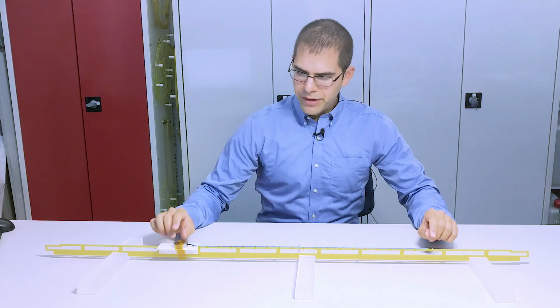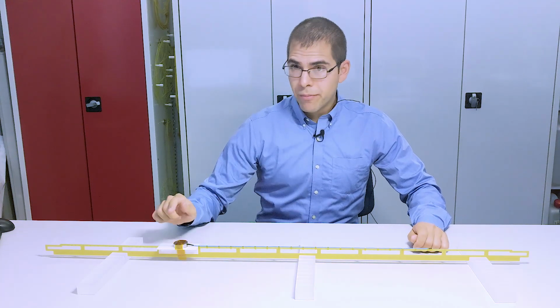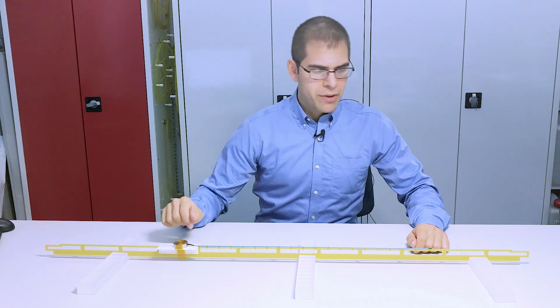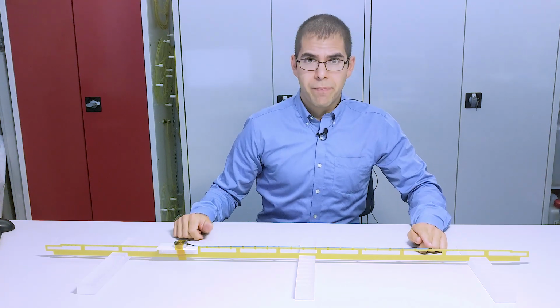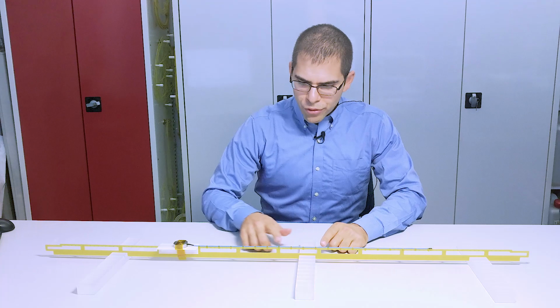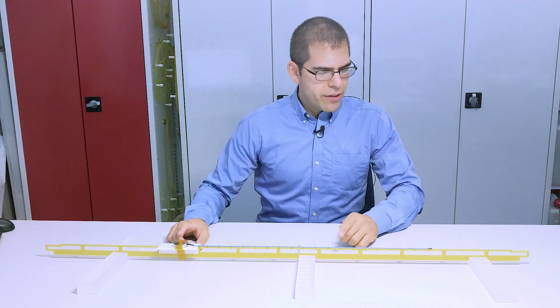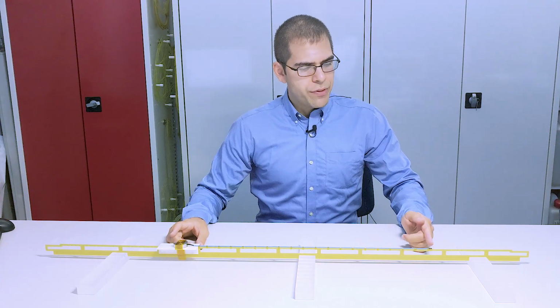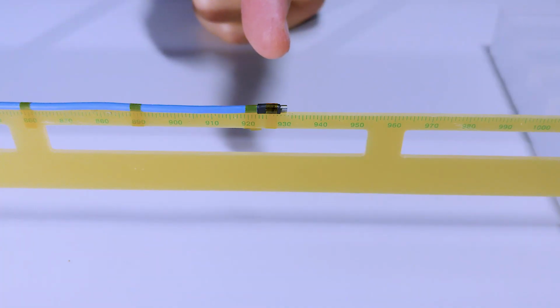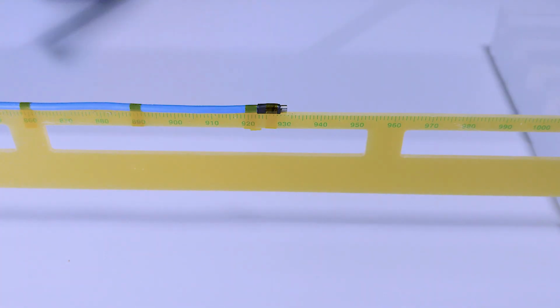The implant is fixed on the racetrack like this. It's important to use non-conductive tape and to avoid covering the electrode tip. Use the ruler along the racetrack to make sure that the electrode tip is lined up with the E-field probe, which will measure the response at the tip. In our case, it's at 930 millimeters, so we put the electrode tip there.